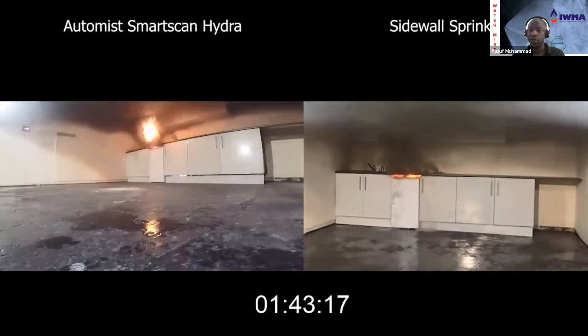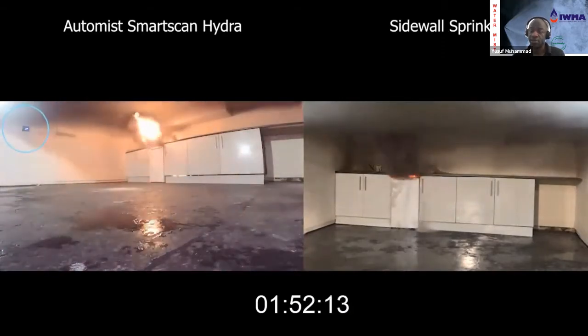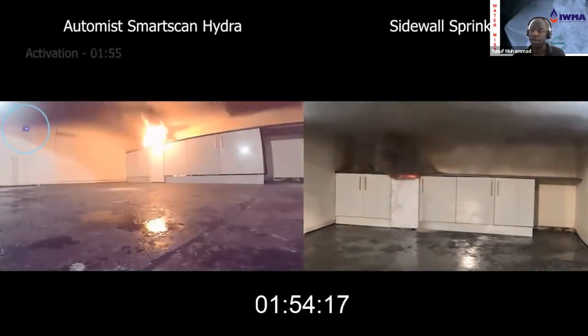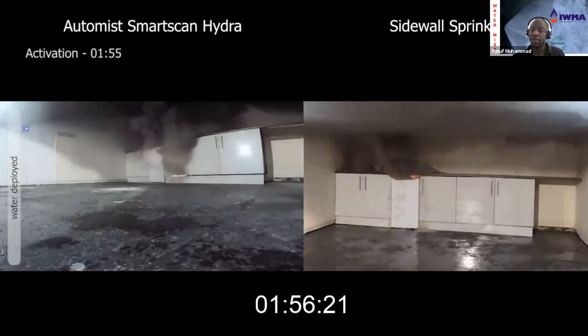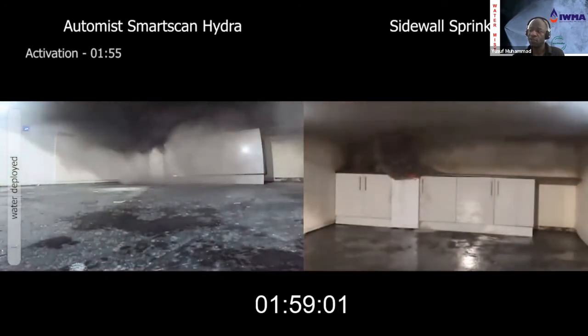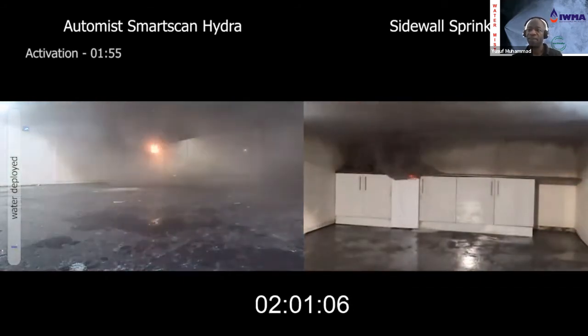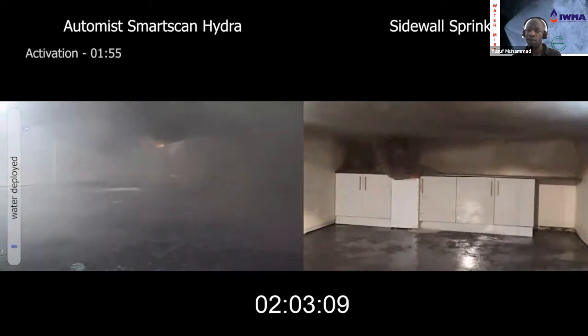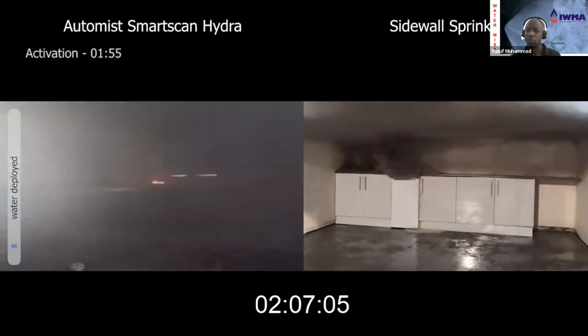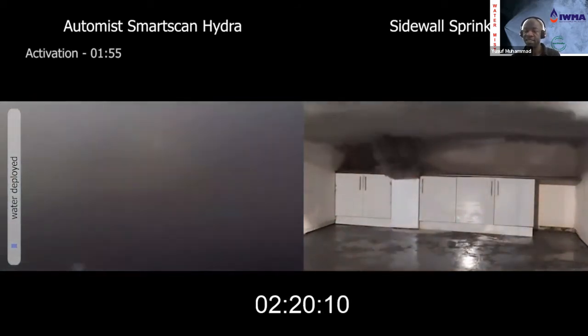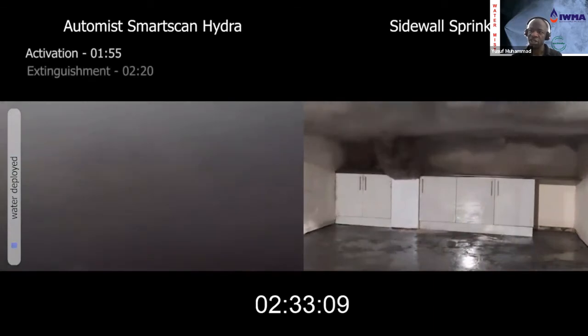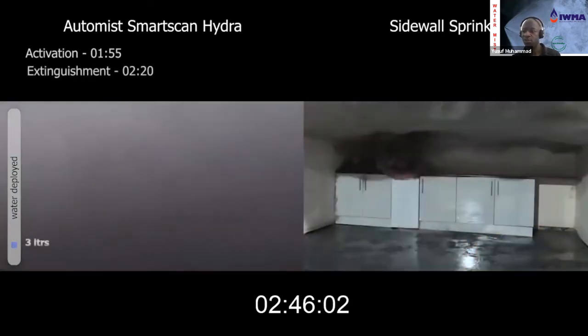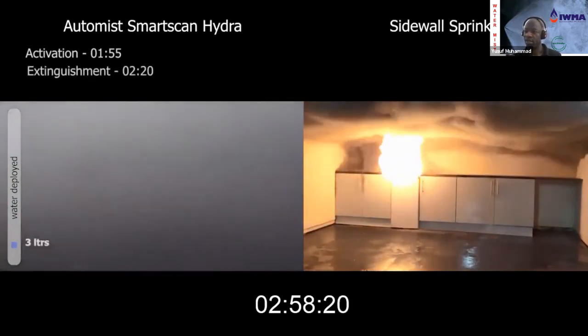And that's because we're using our electronic sensor, which is looking for change in temperature over time, as opposed to our ceiling-mounted glass bulb, which is looking for the ceiling temperature to go above a certain threshold before it activates.